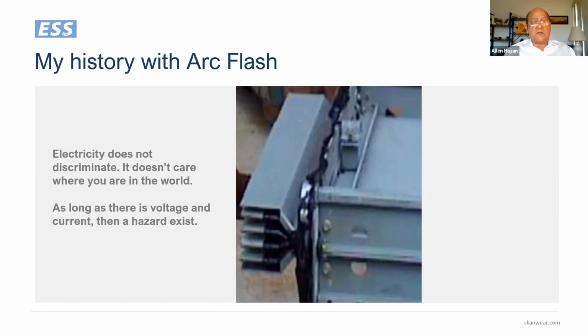In the video, it was a screwdriver, but here the phases are close enough that the crocodile connectors, or alligator clips as we call them in the US, can actually go cross phases. This bus duct was already connected to the transformer, and there were no breakers or fuses between this point on the bus duct and the transformer.